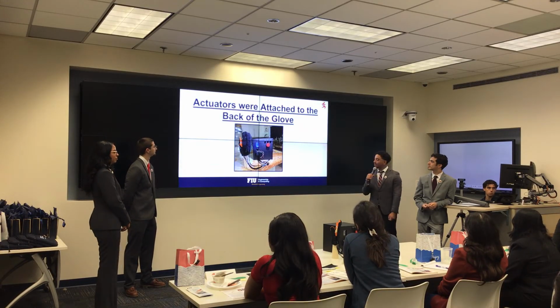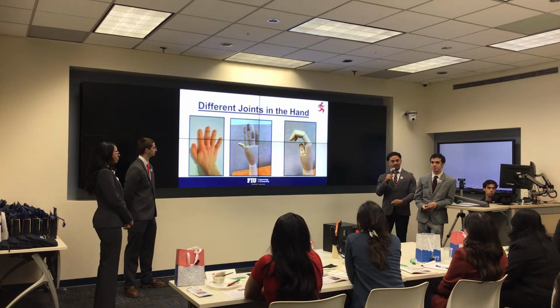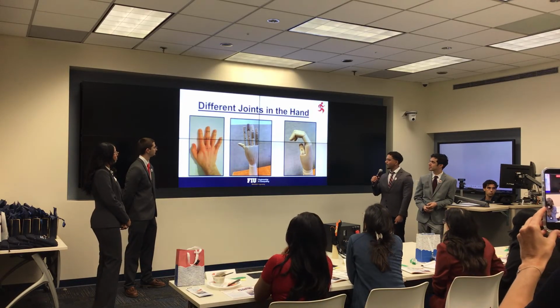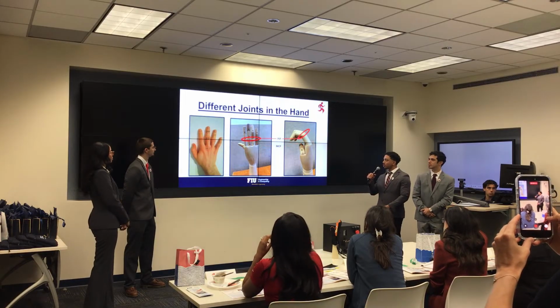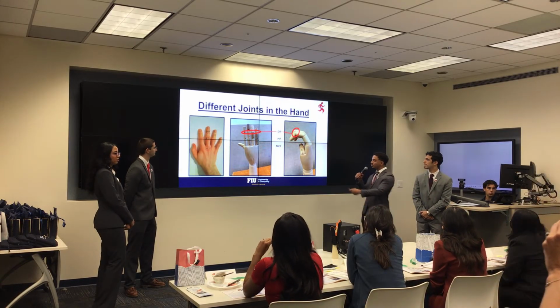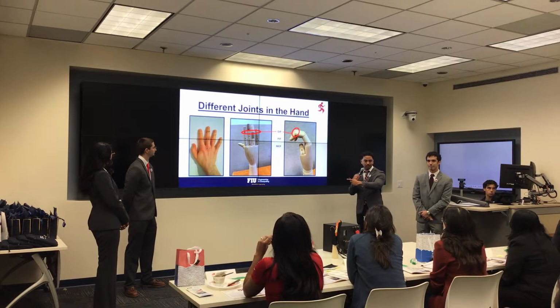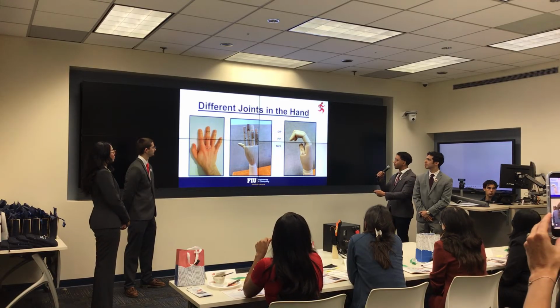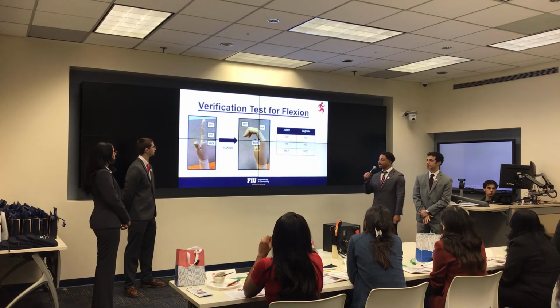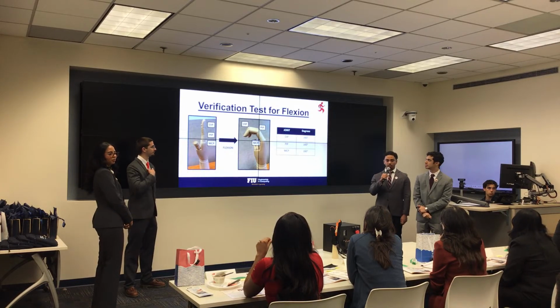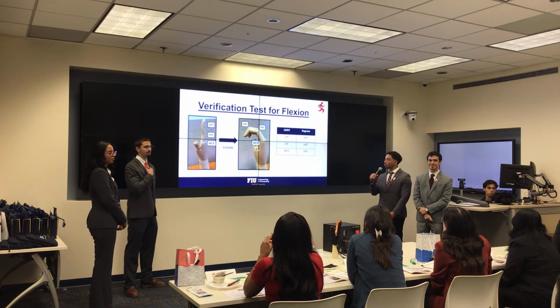So knowing that, we then mount it onto the glove with our control box to then begin verification test. So I want to begin first by talking about the anatomy of the hand before we talk about verification. So we're going to look at the 4 primary digits on the wood hand and fixture. So it's going to be the MCP joint, the PIP, and the DIP joint. So then from this, we're going to start our verification. So our verification test has an acceptance criteria of a minimum of 60 degrees for all the joints. And we're going to try the flexion out.